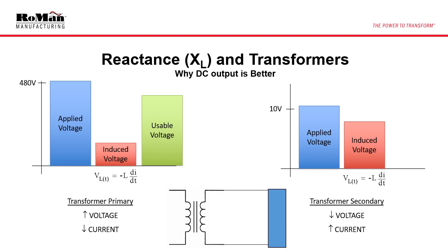However, with the low voltage secondary, the induced voltage, which is a function of the higher current, creates a higher opposing voltage. This is why high amperage alternating current in a transformer secondary exaggerates reactance losses. The impact of reactance on the usable voltage of a secondary is exaggerated and should be avoided. With IGBT MFDC system, we rectify the transformer output directly to direct current and eliminate these losses.